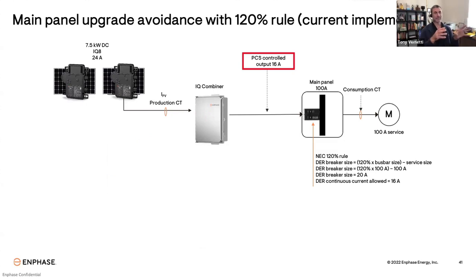So another example of the downside of this approach. If we increase the system size further so its potential output is well above the backfeed limit, the energy production is going to be significantly lower than without PCS. So in this example, the PV system is rated at 24 amps, but PCS limits the backfeed to 16 amps. So during times of high irradiance and production, the current or power of the PV system could be significantly curtailed or reduced.